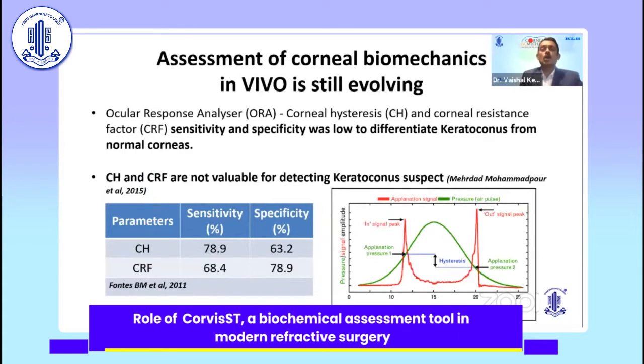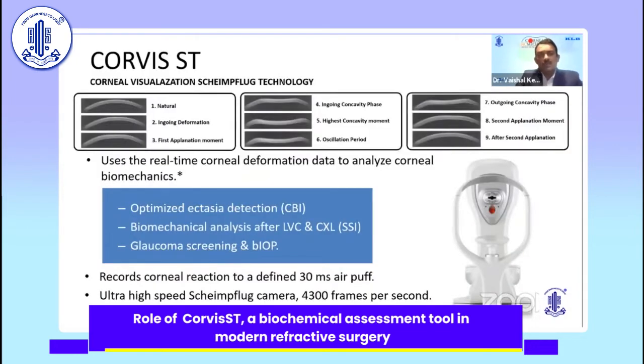Assessment of corneal biomechanics in vivo is still evolving. ORA was the first tool, but the CH and CRF sensitivity and specificity were found to be very low to differentiate keratoconus from normal corneas. The Corvis ST, or Corneal Visualization Scheimpflug technology, uses real-time corneal deformation data to analyze corneal biomechanics. It records the corneal reaction to a defined 30-millisecond air puff — a defined force used to deform the cornea, unlike the previous generation ORA.